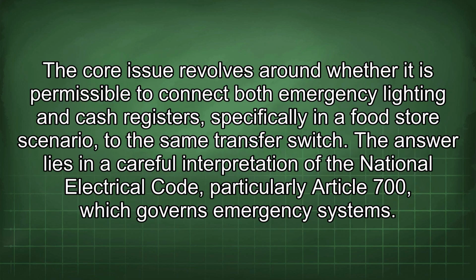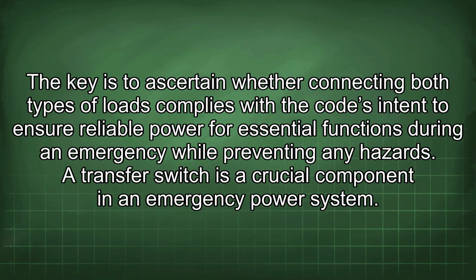The core issue revolves around whether it is permissible to connect both emergency lighting and cash registers, specifically in a food store scenario, to the same transfer switch. The answer lies in a careful interpretation of the National Electrical Code, particularly Article 700, which governs emergency systems. The key is to ascertain whether connecting both types of loads complies with the code's intent to ensure reliable power for essential functions during an emergency while preventing any hazards.